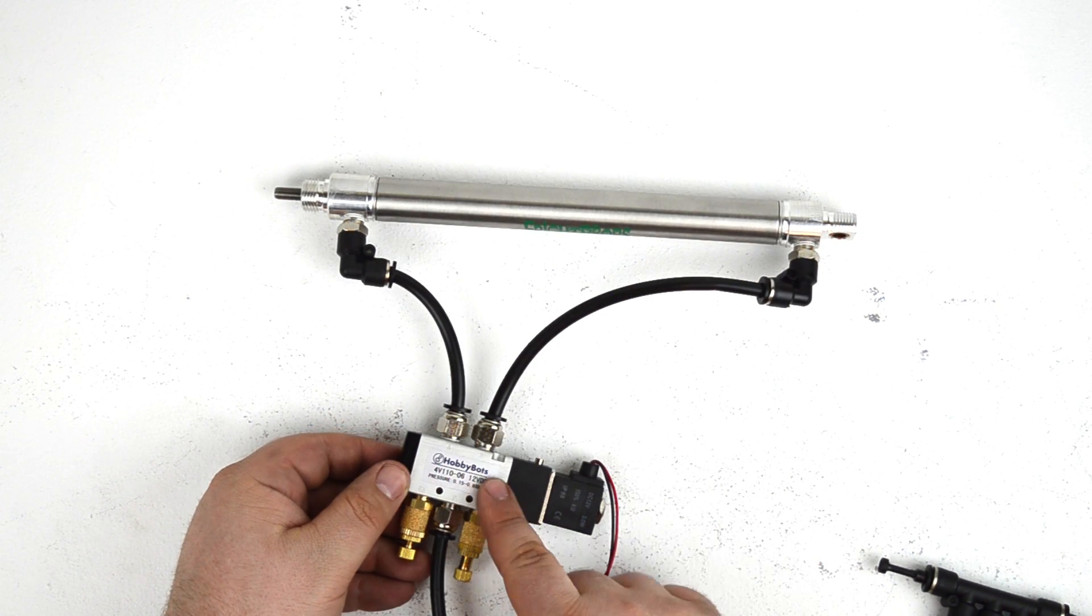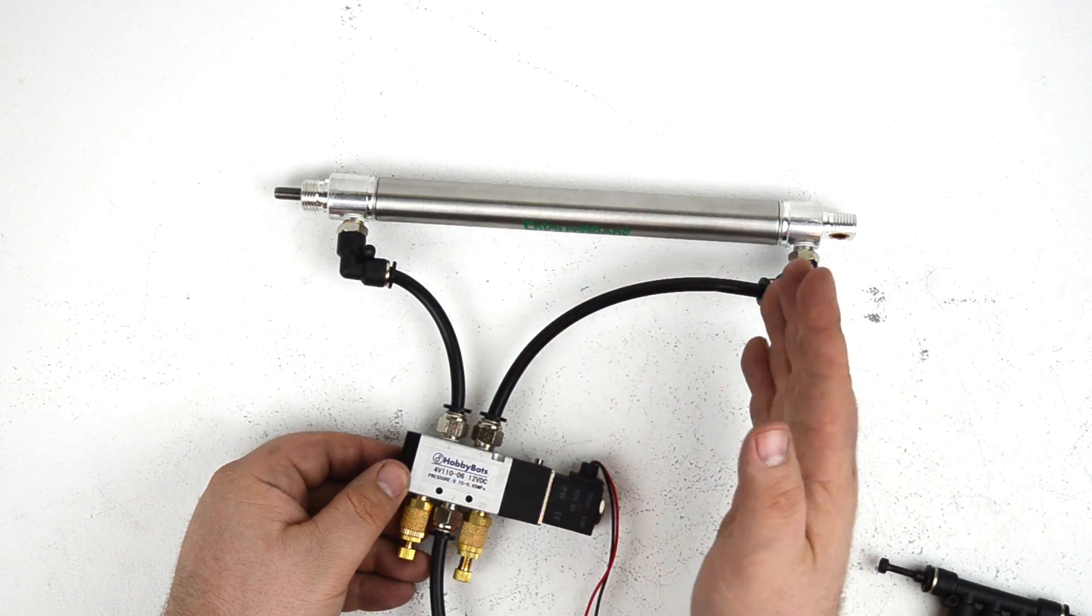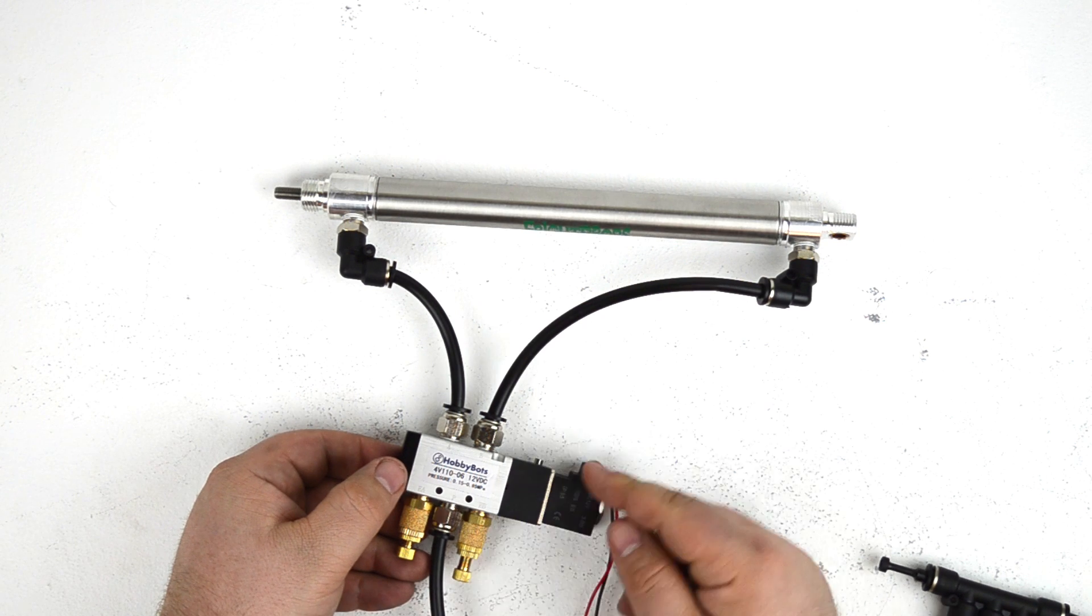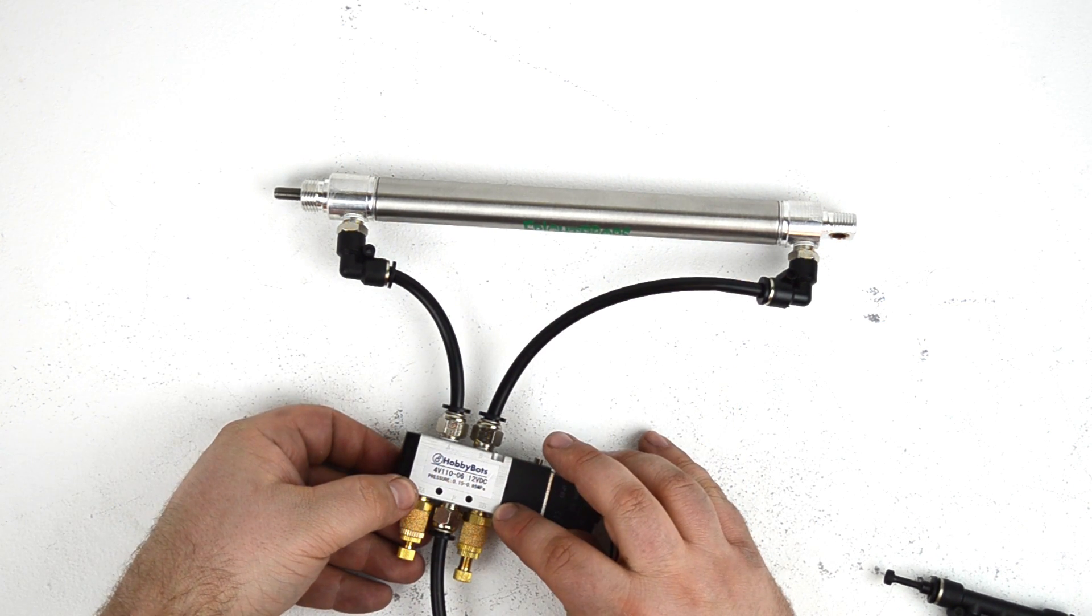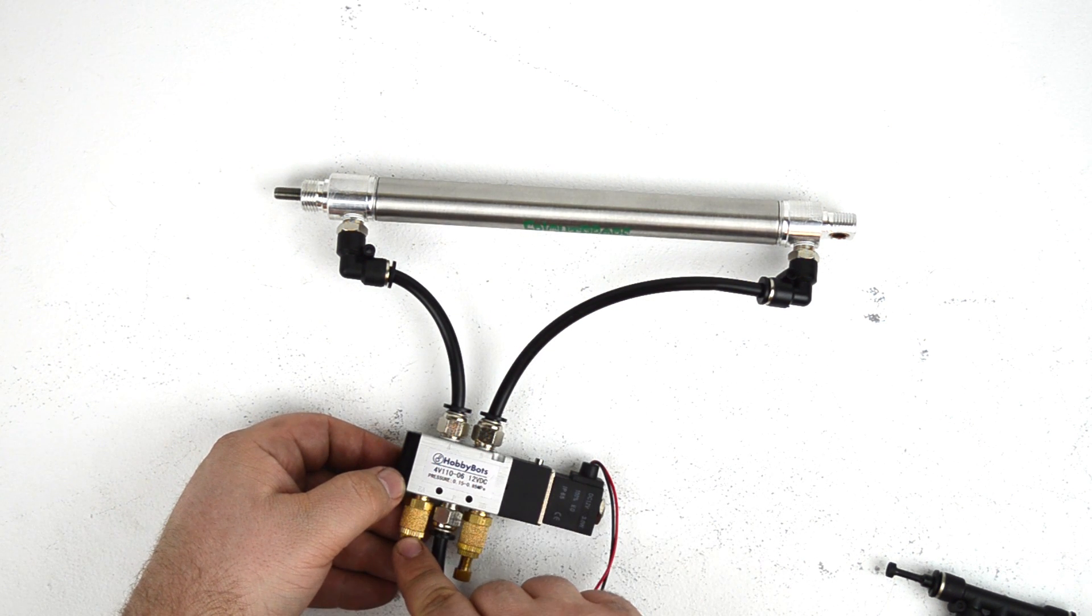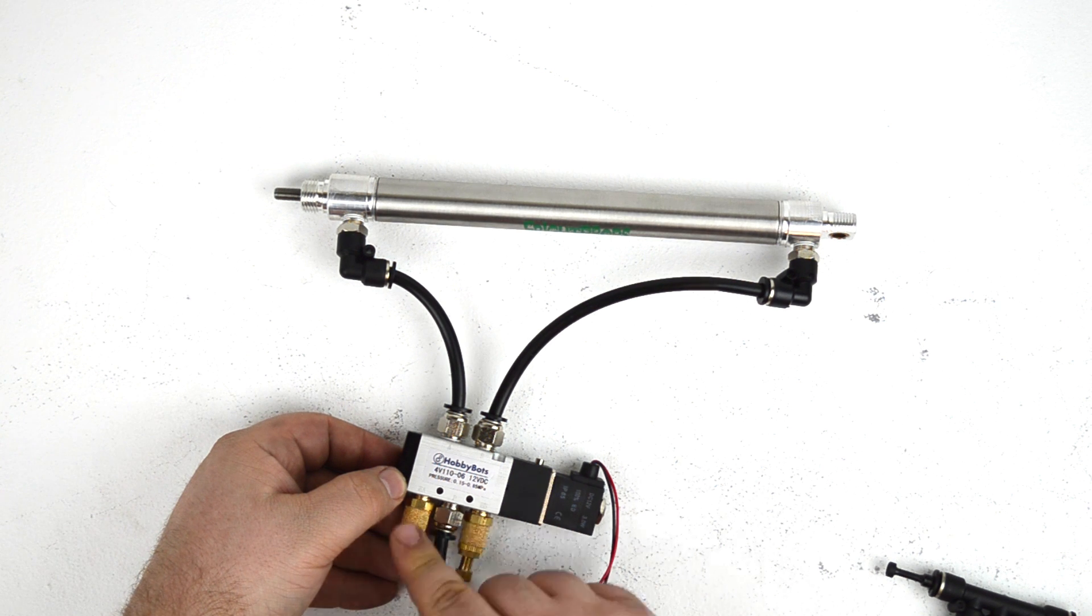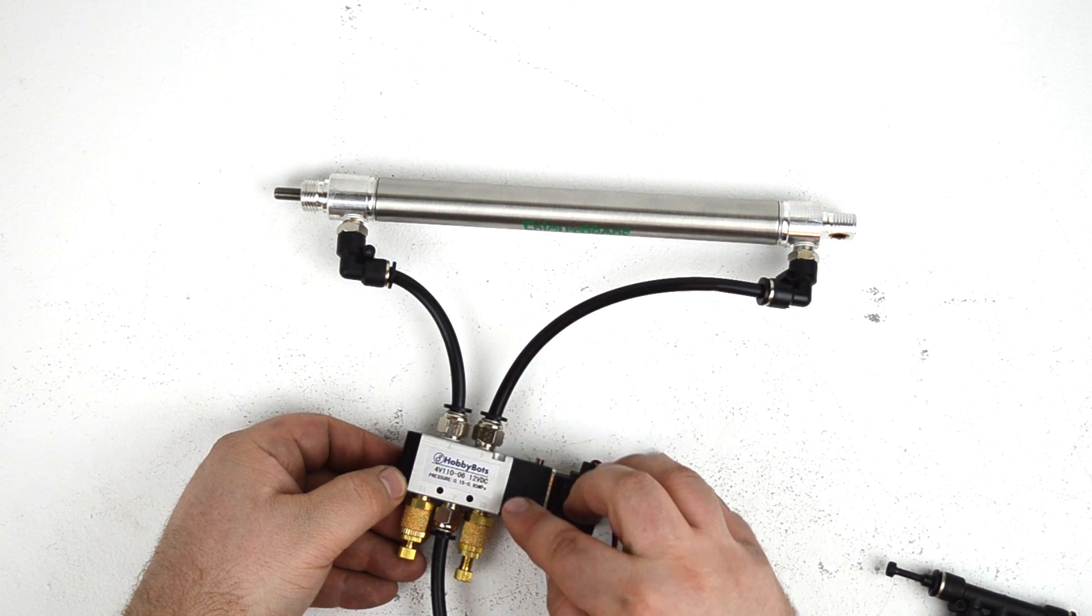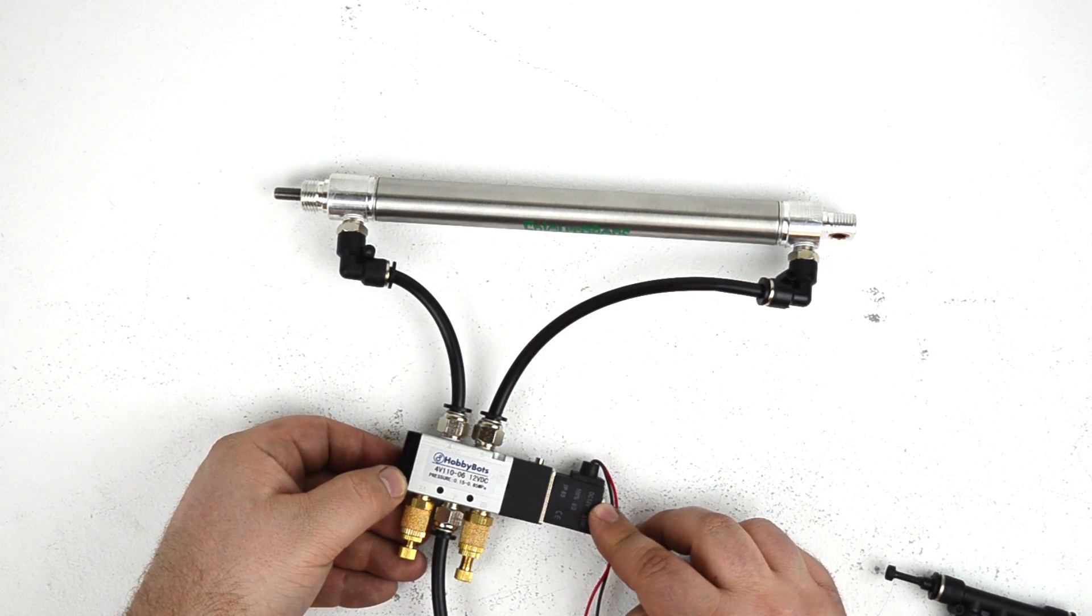Because this is a double acting valve and a double acting cylinder, you can control the speed both of the extension and retraction on the solenoid itself. Because this solenoid has five ports, it has two exhaust ports, one for each output. So you can control the exhaust speed of output A with exhaust A and the exhaust speed of output B with exhaust B. Thereby controlling both the extension and retraction of the cylinder.